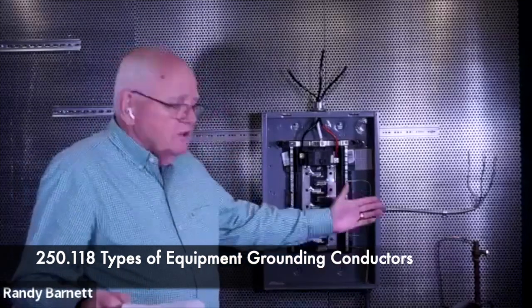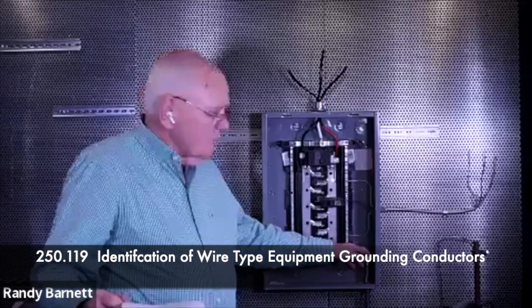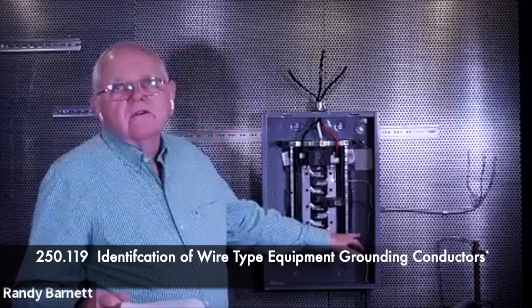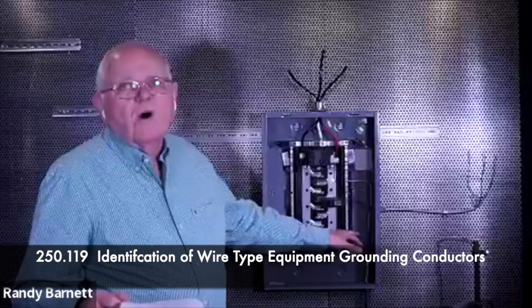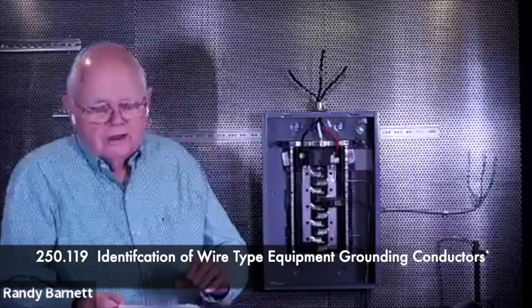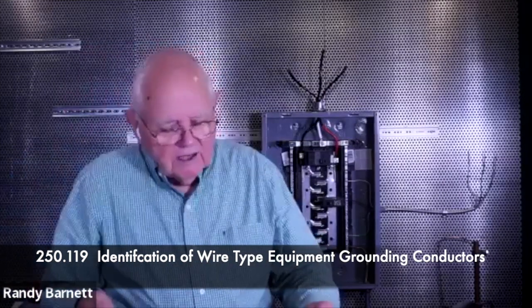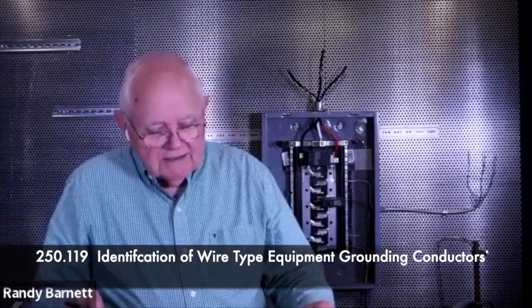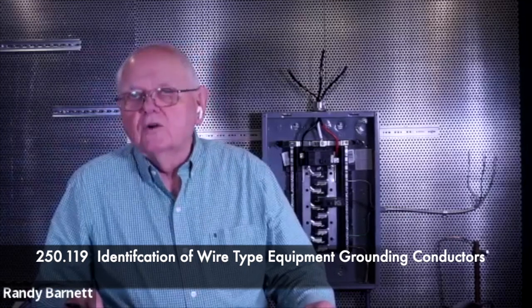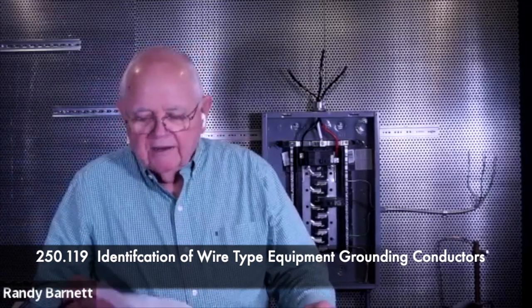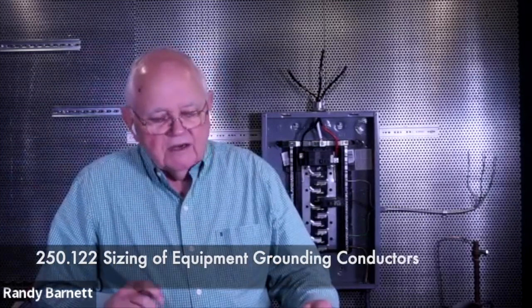So I can use things like conduits, metal raceways, can I, for my equipment grounding conductor? I may not have to run the green equipment grounding conductor in this case, or a separate wire type, we would call it, equipment grounding conductor. 250.119 talks about identification of the wire type equipment grounding conductors. And then 250.122 gets into the sizing of our conductors.